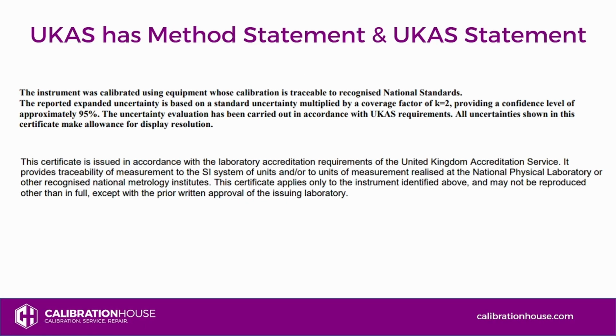A UKAS certificate also has a method statement and a UKAS statement. So the method statement is explaining how the calibration was performed, and the UKAS statement is stating that the certificate is issued in accordance with the UKAS accreditation requirements. A traceable certificate obviously wouldn't have the UKAS statement. It may have a method statement, but not normally.